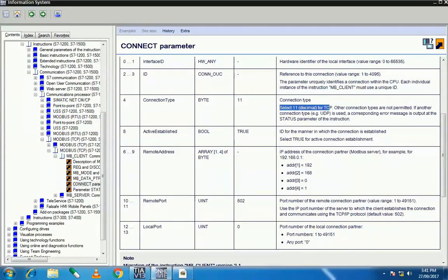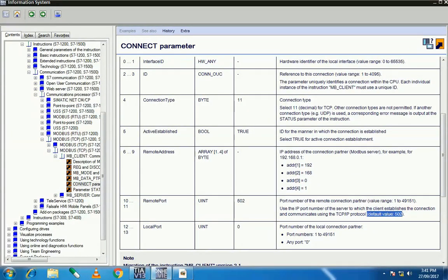Next is active connection establish — select true for active connection. Remote address is where we set our Modbus server address. Remote port is the port number of the remote connection partner, and by default we set the value 502. Local port is the port number of the local connection partner — if you are communicating on any other port, just set it to zero.